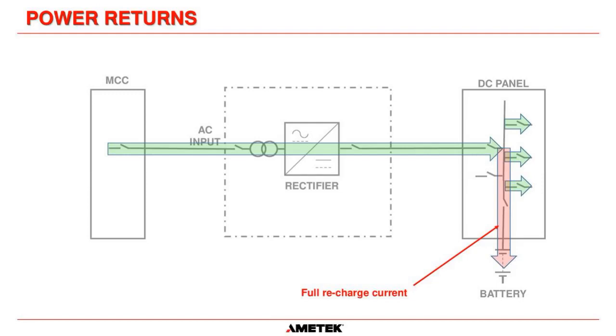Now, if the power comes back on again, so 480 is now available, once again, no switching is involved. The rectifier charger will come back on again immediately. And what it will do is it will start feeding the load circuits, because remember, it has a higher voltage of 135 volts. And it will supply full recharge current back into the battery. So if it's designed correctly, then the battery will be fully recharged and it will have the ability to supply power to your load circuits as well.